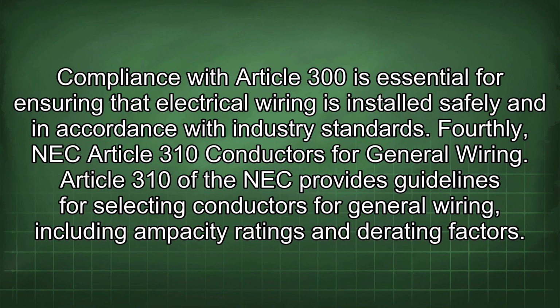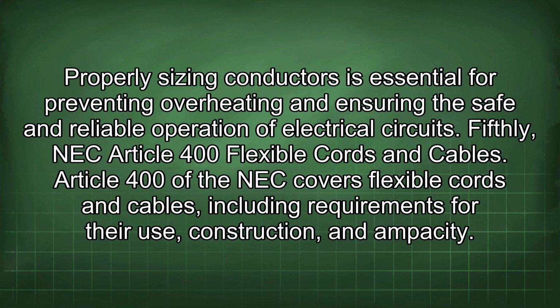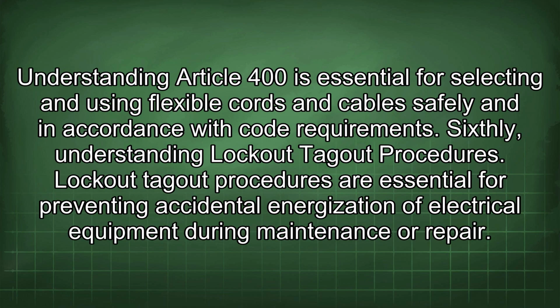Fourthly, NEC Article 310 conductors for general wiring. Article 310 of the NEC provides guidelines for selecting conductors for general wiring, including ampacity ratings and derating factors. Properly sizing conductors is essential for preventing overheating and ensuring the safe and reliable operation of electrical circuits. Fifthly, NEC Article 400 flexible cords and cables. Article 400 of the NEC covers flexible cords and cables, including requirements for their use, construction, and ampacity. Understanding Article 400 is essential for selecting and using flexible cords and cables safely and in accordance with code requirements.